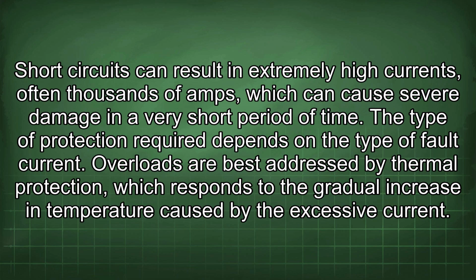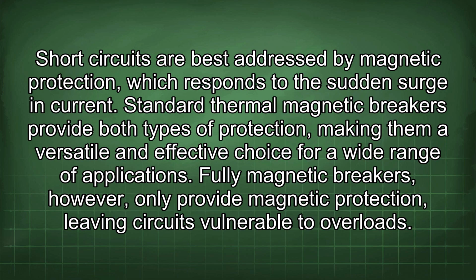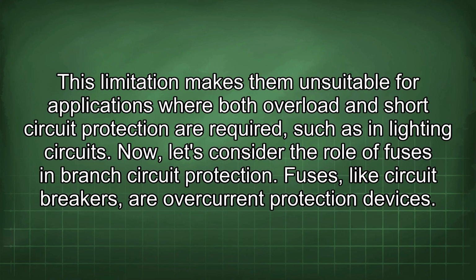Overloads are best addressed by thermal protection, which responds to the gradual increase in temperature caused by the excessive current. Short circuits are best addressed by magnetic protection, which responds to the sudden surge in current. Standard thermal magnetic breakers provide both types of protection, making them a versatile and effective choice for a wide range of applications. Fully magnetic breakers, however, only provide magnetic protection, leaving circuits vulnerable to overloads. This limitation makes them unsuitable for applications where both overload and short circuit protection are required, such as in lighting circuits. Now let's consider the role of fuses in branch circuit protection.